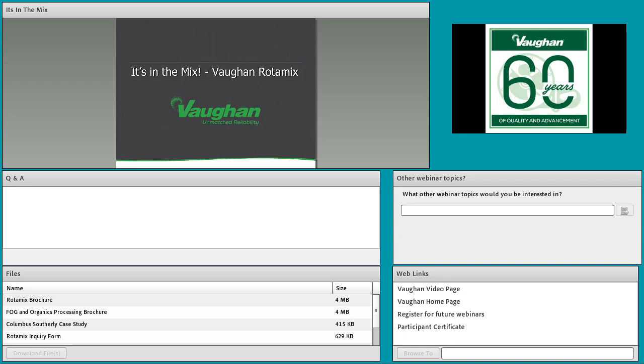Yeah, so generally we will size the equipment based on our experience, and you always need to have a first guess. You're going to take the best information available and provide an initial design, and then from there we'll start to look at CFD to better refine that design and make sure that, okay, this is what I think is going to work, but now I'm going to verify it, using that scientific method and saying, okay, I think this is the design, but now I'm going to validate it. And through that, we might iteratively end up in a much more efficient layout than what we initially had thought would work. But generally, we'll have an initial design before we do the CFD modeling, just because the chicken has to come before the egg, so to speak.